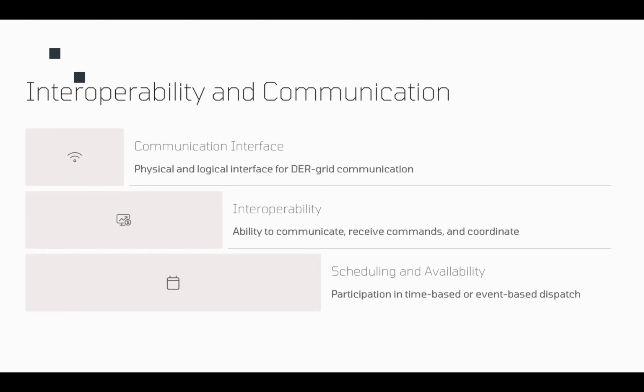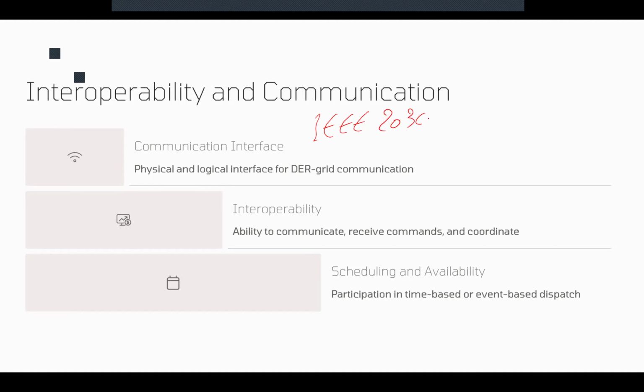Now, when we talk about the communication interface, it's basically the physical and logical link between the DER and the utility grid or the grid management system, which basically enables data exchange, remote control, or firmware updates. Okay. Now, the requirement for these communication interfaces that are defined in IEEE 1547 is that they have to follow some mandatory standard protocols. Okay. One standard is IEEE 2030.5, which we call the Smart Energy Profile.